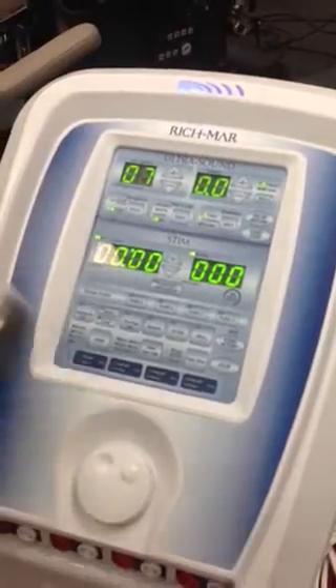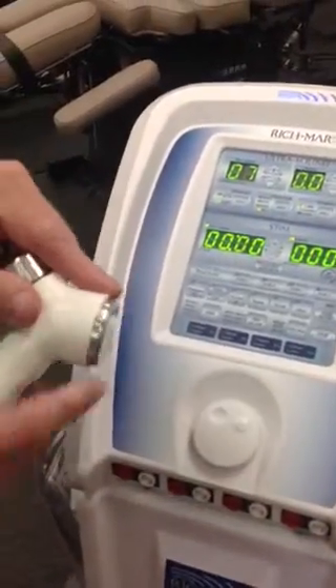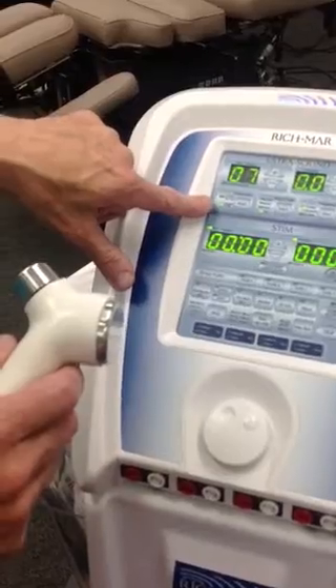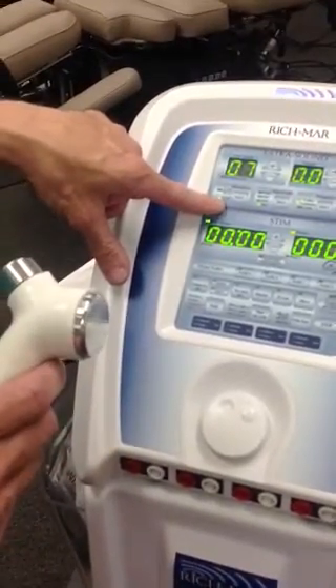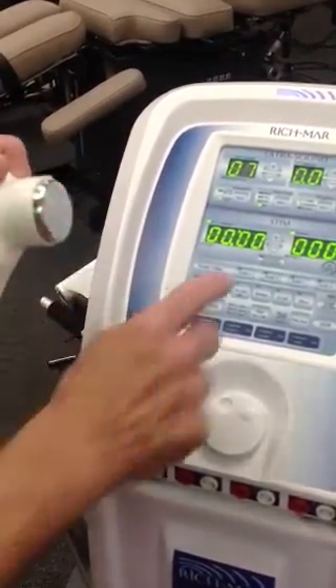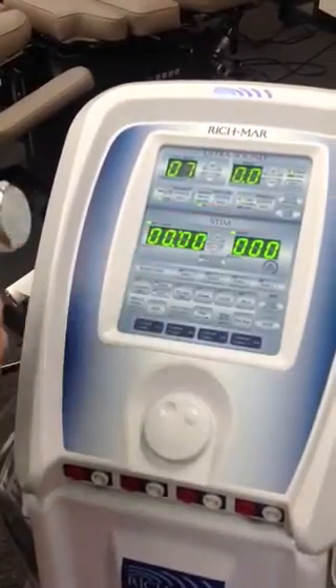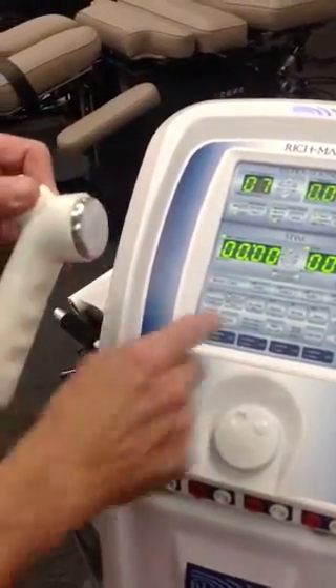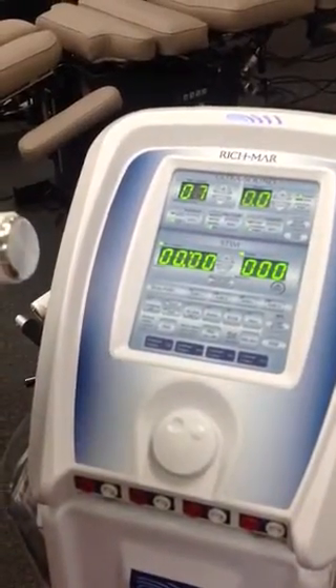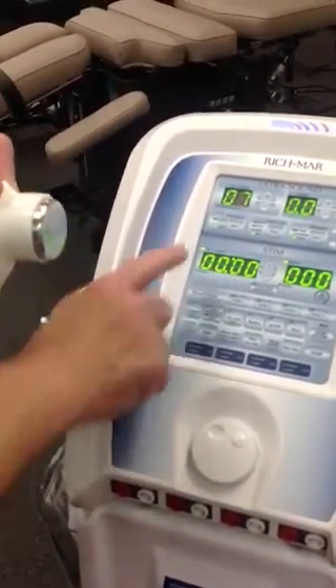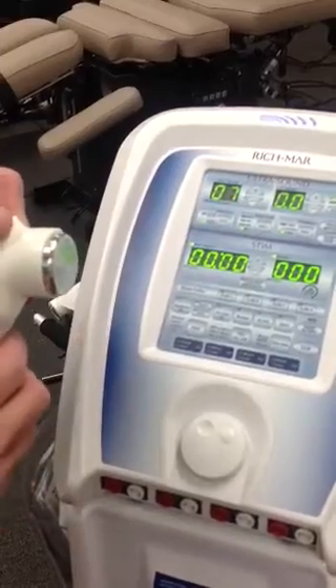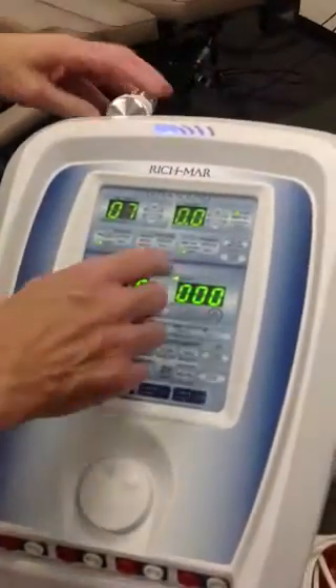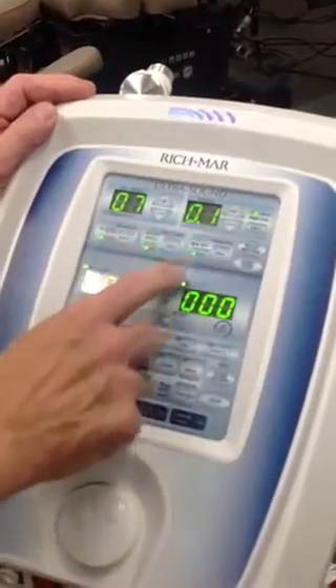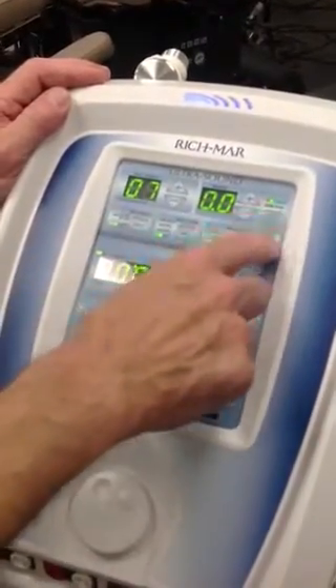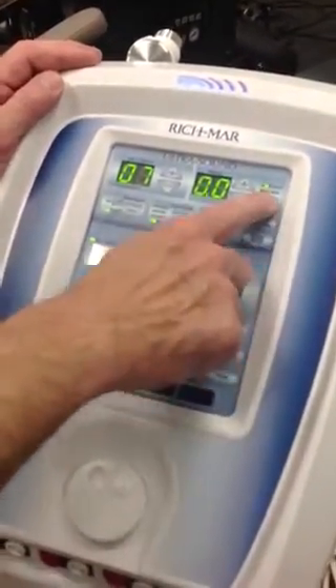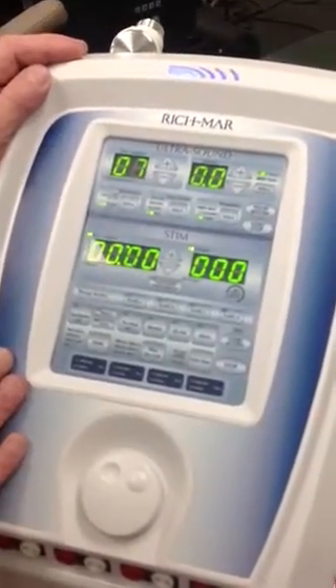But in this case, you choose your ultrasound, and here it's our 5 centimeter head. I know that because our 5 cm light is on, not our 2, and we've chosen 1 megahertz. So we're going to get deep ultrasound with our 1 megahertz, or we're going to get superficial ultrasound with our 3 megahertz, all through the 5 centimeter sound head. Okay? And then we have our watts, or watts per centimeter squared, and there's our selection there, and almost everybody leaves it on watts per centimeter squared.